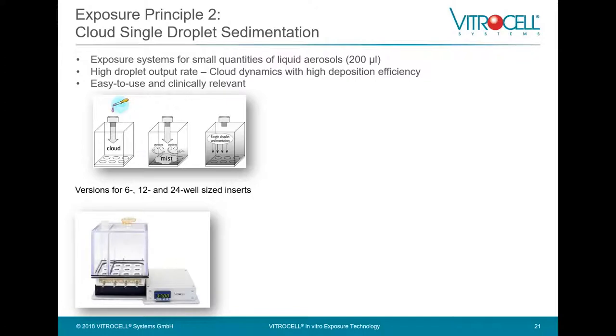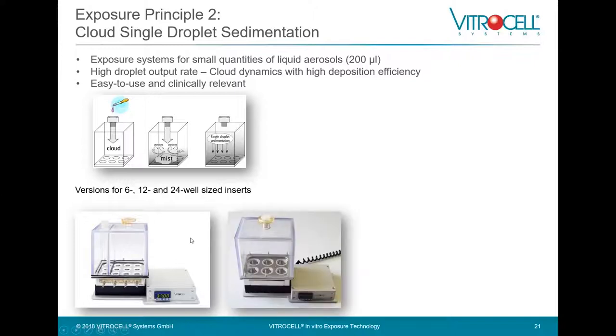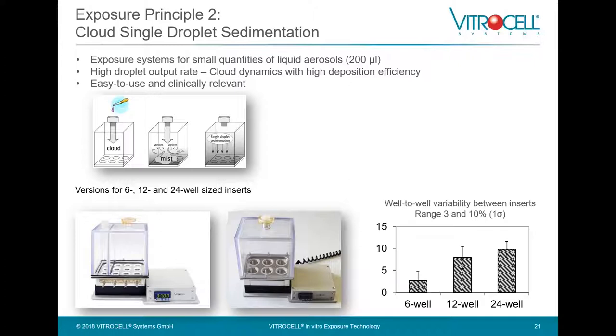Cloud systems are available in various versions for six, 12, and 24 well-sized inserts. Here you see a typical Cloud 12 and a Cloud 6 for six well-sized inserts. The graph shows a nice, low well-to-well variability: in the six-well format it's about three percent, on the 12-well it's about eight percent, and on the 24-well format it is about ten percent — which is a very good value for in vitro experiments.